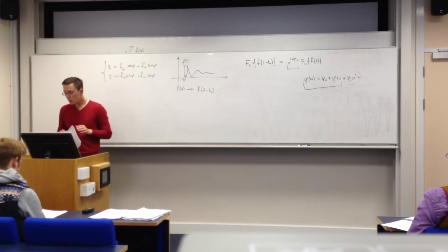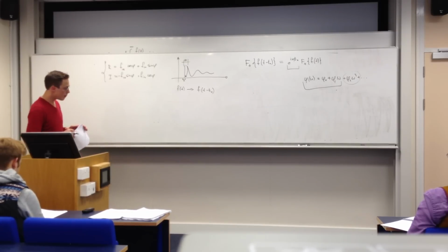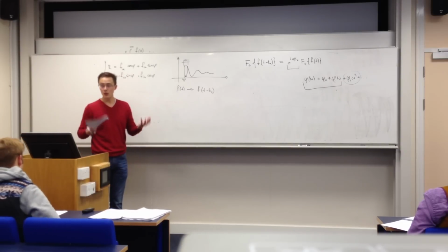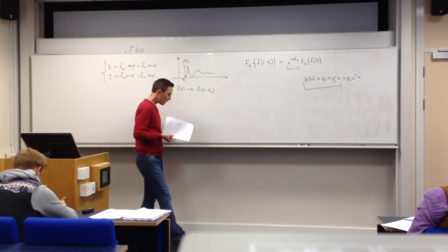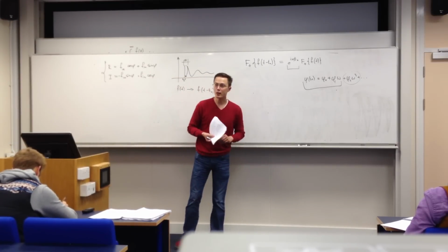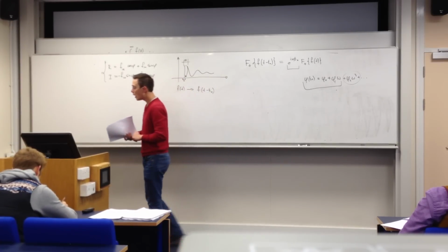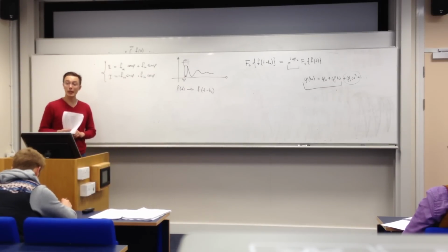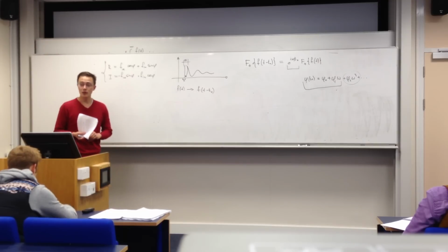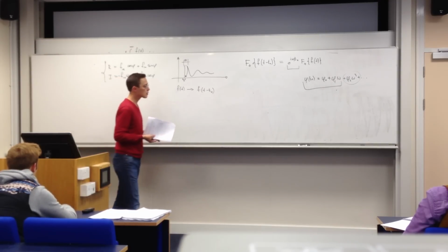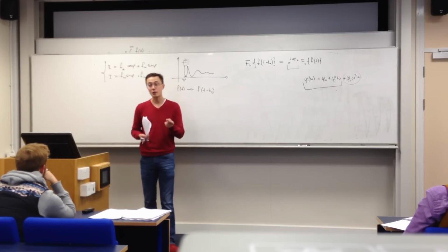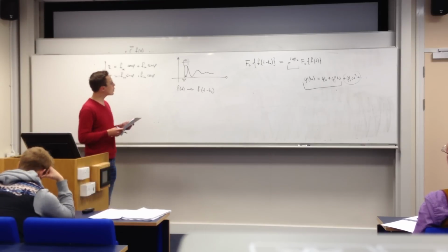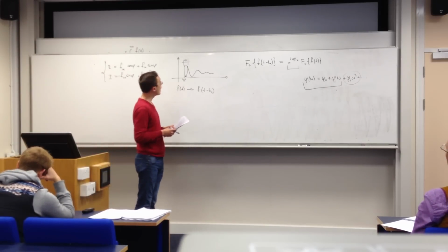It is often the case in fluorine spectroscopy that parts of the probe are made of Teflon, which is a fluorocarbon, and a fluorocarbon at a huge concentration, something like 100 moles per liter, has a signal. The signal decays extremely quickly, but because there's so much of it, 100 molar concentration compared to maybe a millimolar concentration of your sample, that's 5 orders of magnitude, the signal, however quickly it decays, will actually show up.